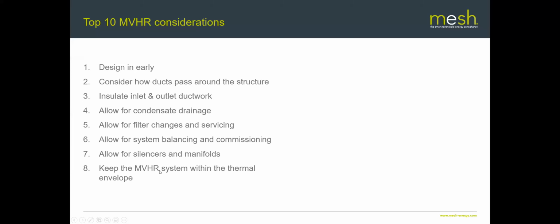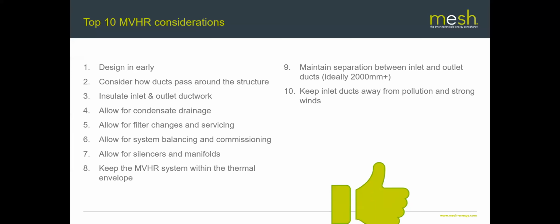If possible, keep the MVHR system within the thermal envelope of the building, and that's to conserve that hard-won energy you've got back. Maintain the separation between the inlet and outlet ducts. So the ducts that go out of the building, obviously what you don't want to be doing is blowing the exhaust air out and then immediately sucking that same air back into the intake. Ideally a couple of meters apart, but they can go a little bit closer than that.